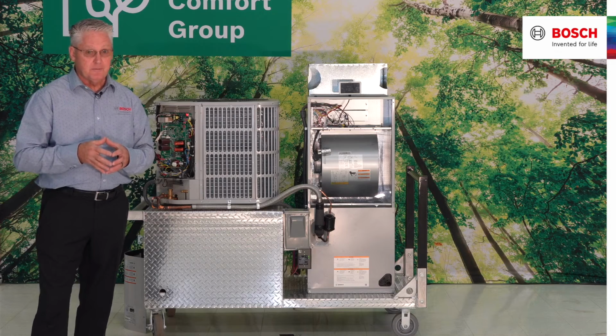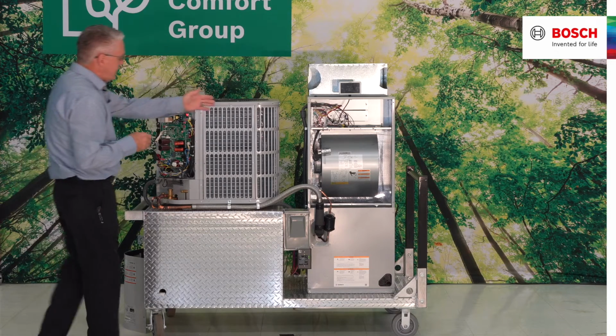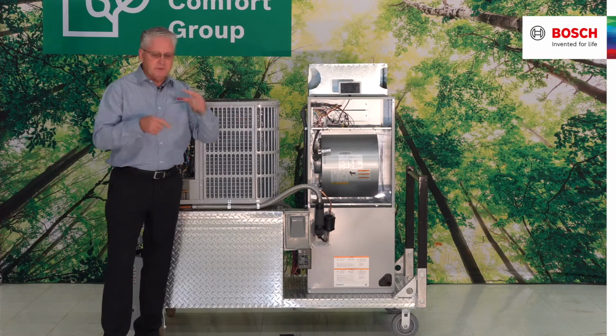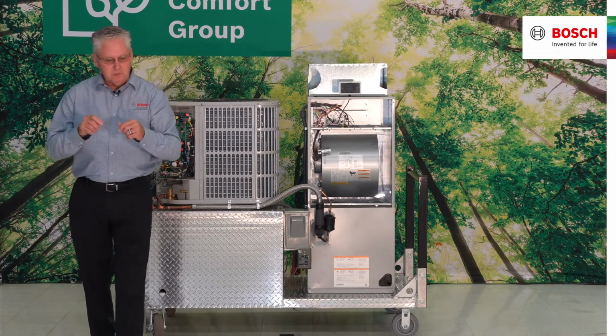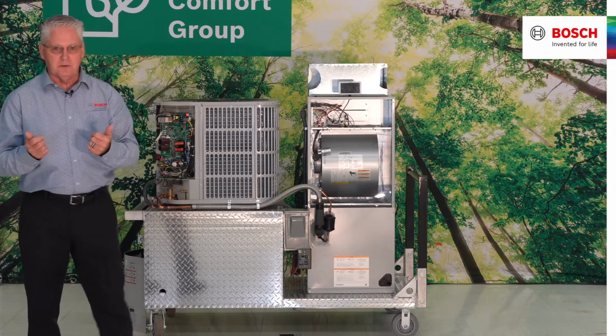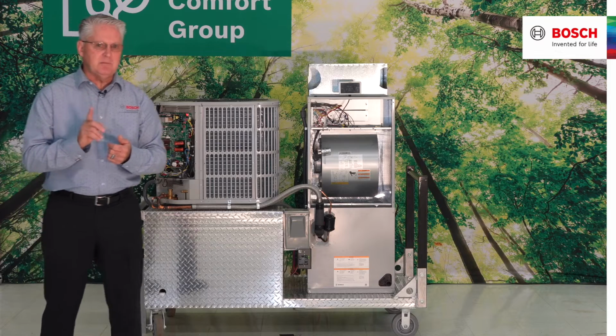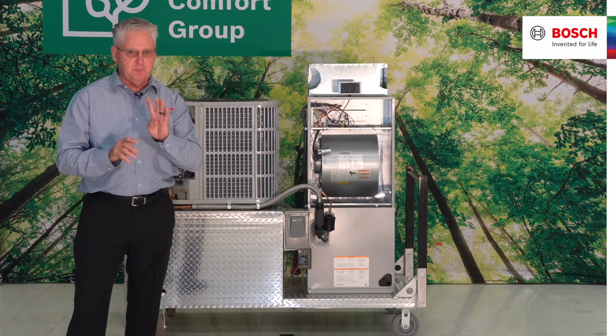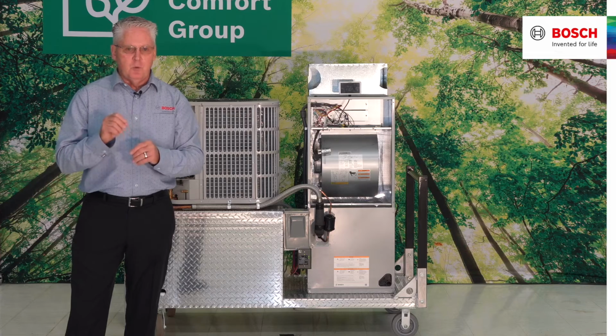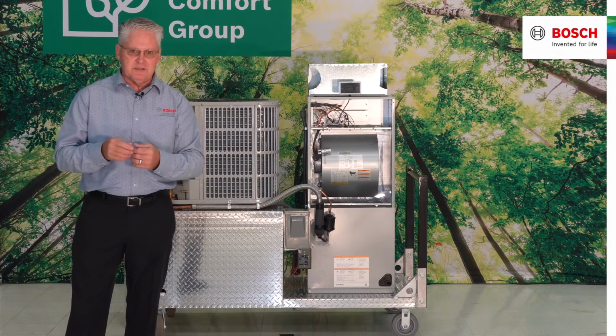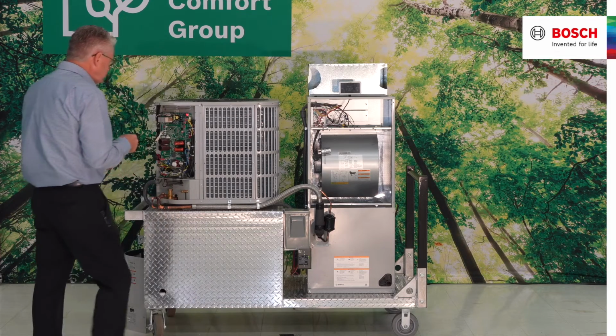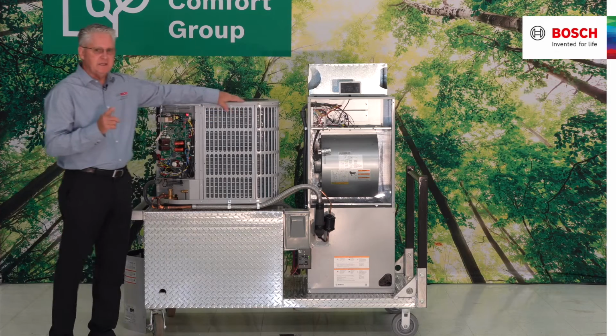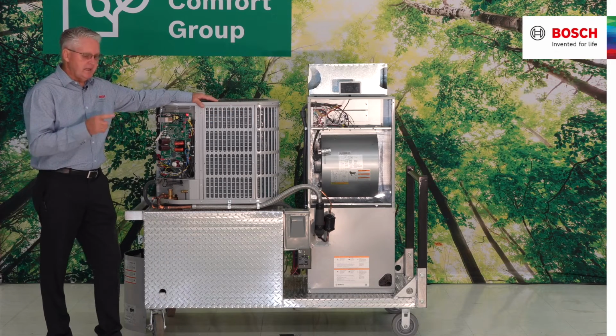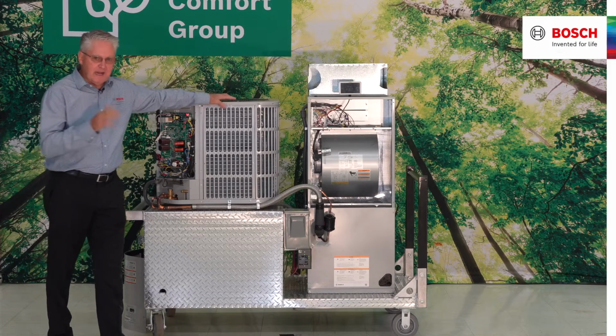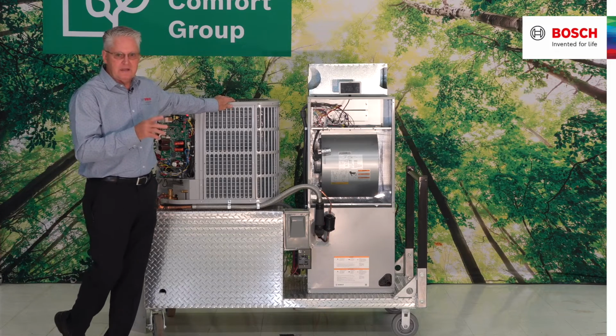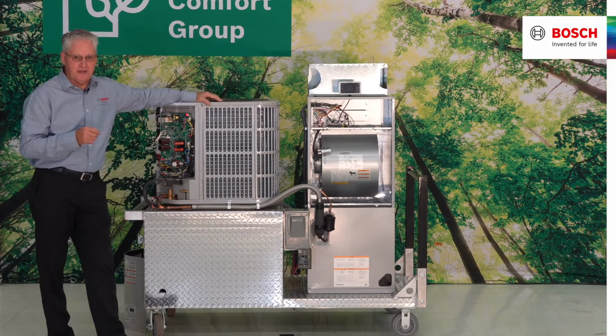And my BVA is a multi-position air handler: upflow, downflow, left-hand, right-hand, horizontal. It has a PSC motor that is a 5-speed, you pick 4. And if you want to, you can upstage or downstage that particular fan motor. But it is a PSC fan motor, so again, it is not a high static blowing device. 0.8 is its max on the static.